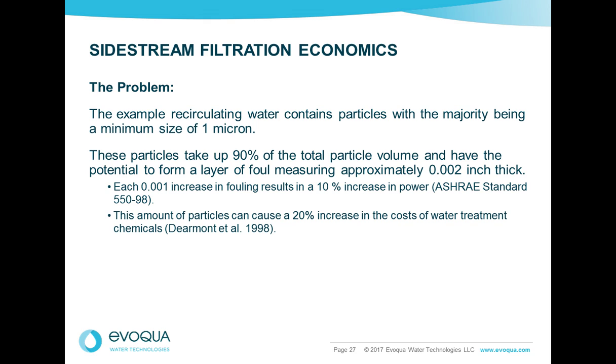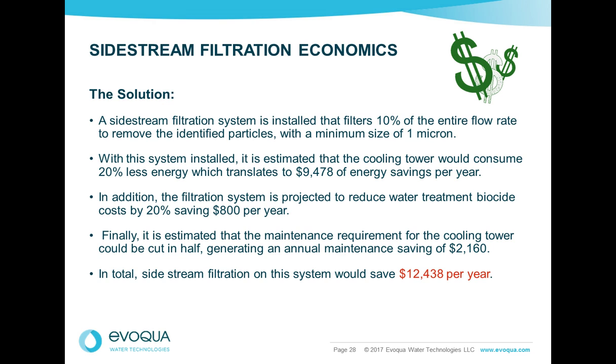Now we know that each 1,000th of an inch can increase your energy cost by 10% and potentially increase your chemical cost by 20%. Also, you may want to note that the ASHRAE handbook states that a 200-ton tower can take in up to 600 pounds of particulate in a season. And obviously here we've got a 400-ton tower. So we're looking at as much as 1,200 pounds of particulate collected in areas like the tower fill and the sump and the low flow areas that Bob talked about earlier.